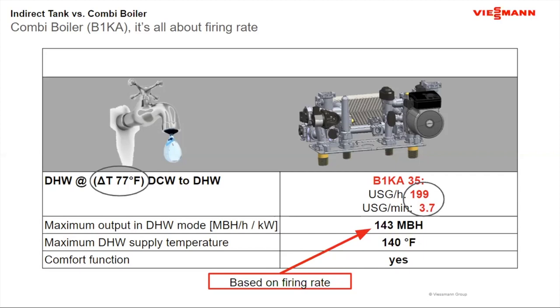When I look at combi boilers, this is what I start to deal with. One other thing about this 77 degree rise, the other thing that I often talk about when somebody says combi is, what's your groundwater temperature? I can get 3.7 gallons per minute on a 77 degree rise. But if I'm in northern New England, where the groundwater temperature is running around 36, 37 degrees, I may have to scale back that 3.7 to maybe 3.3 or 3.2, so that I can give them the right water temperature. So that also is one of the discussion points when we're looking at what's the right application for it.